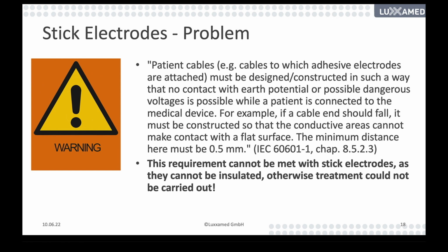Especially for this problem I talked about with electric safety, to explain it to you, there is one clause, 8.5.2.3, in the 60601 Part 1, and it is quite simple. If you have the cables or the stick electrodes on the patient to work with them, or also the adhesive electrodes, but this especially is for the stick electrodes, and you work with them, and maybe one electrode falls down and gets contact with an earth potential or a dangerous voltage while the patient is connected to the medical device or microcurrent device, this is of course not allowed.